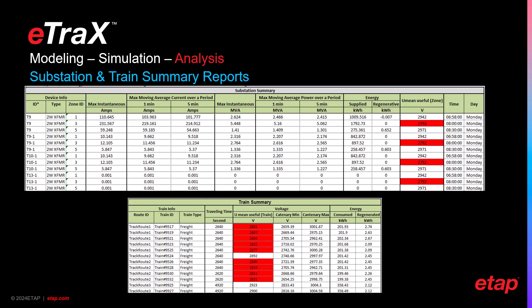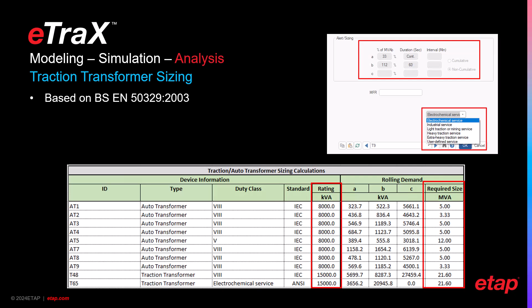Another highlight is that we understand sizing equipment is not easy, because railway equipment feeds moving loads. That means there might be peaks, and you need to consider the time duration when doing the sizing. In eTrax, we honor the BS EN 50329 standard, where you can select the train service type, for example light service, heavy service, extra heavy service, and so on. Based on the standard, ETAP can calculate the required size for the train, considering the time duration, the intervals, and the percentage of the MVA base defined by the standard. With this feature, you can tell whether the design of your equipment is undersized or oversized.